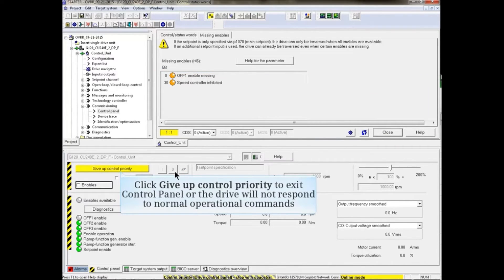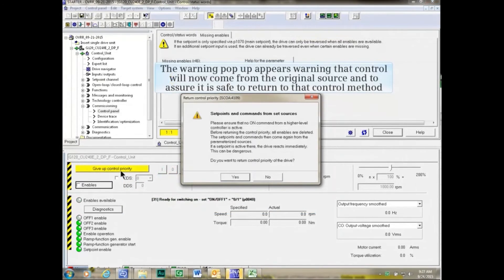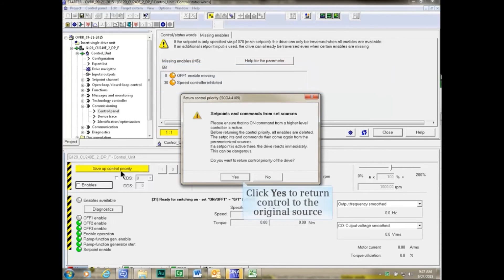To exit control panel, you must first give up control priority or the drive will not respond to normal operational commands. Click the Give Up Control Priority button. The warning pop-up appears warning that control will now come from the original source and to assure it is safe to return to that control method. Click Yes to return control to the original source.